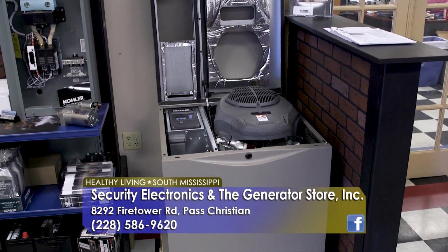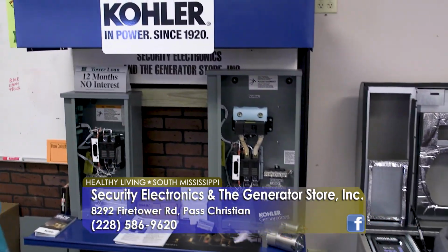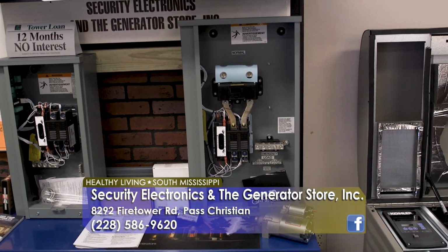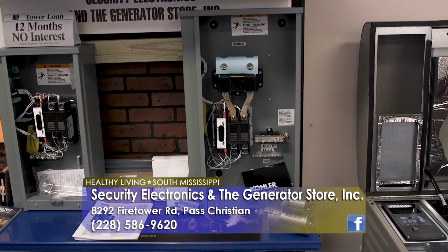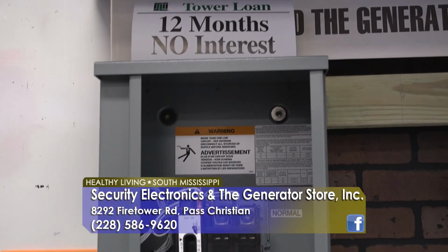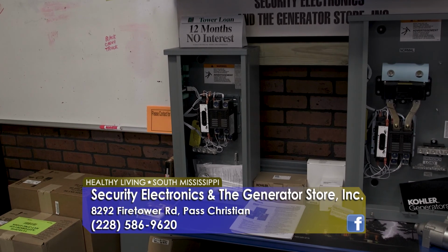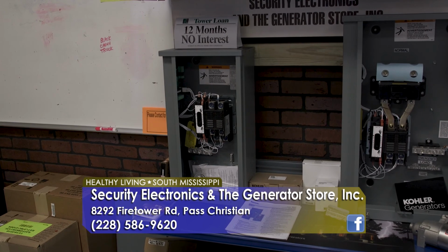comfortable. Now, is this part here part that goes with the generators? Yes, these are some of our transfer switches. This is a service entrance rated transfer switch that can hook directly to a meter, and then you don't have to have a costly electrical box on the outside of the building. In an existing situation, we've got this one on the left is non-service entrance rated, so if you had an existing panel that you have a main breaker in, we could feed to this, and this will feed your essential power panel. There's just a lot of different options.